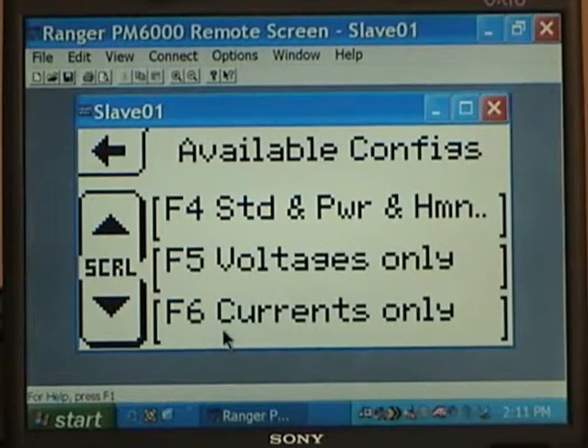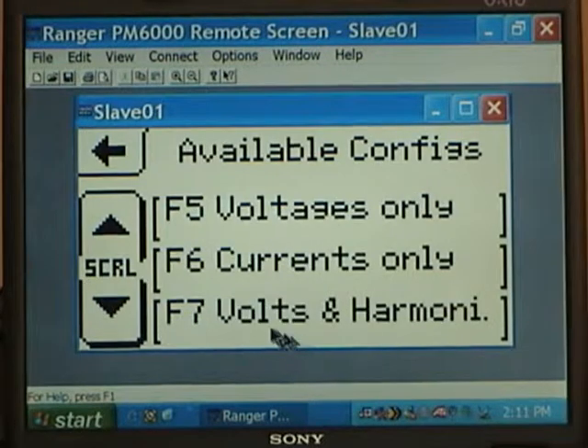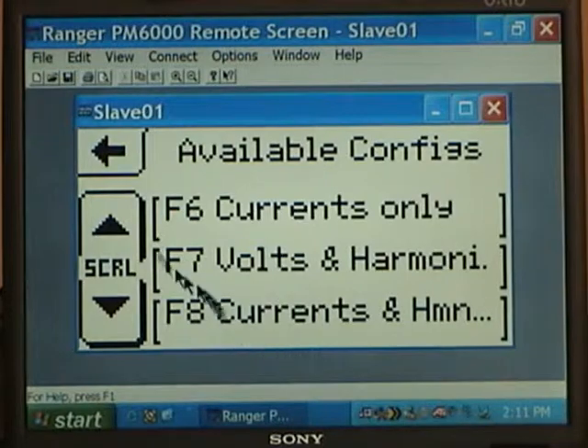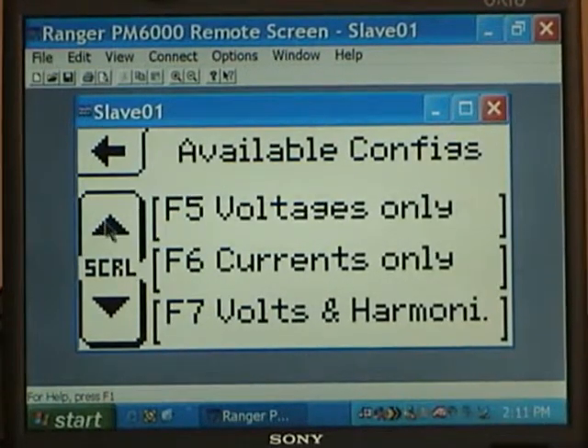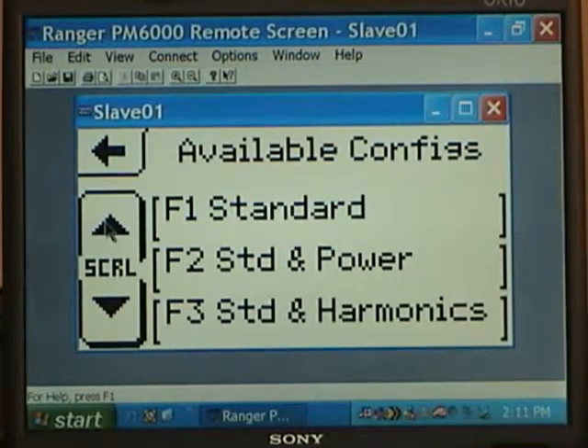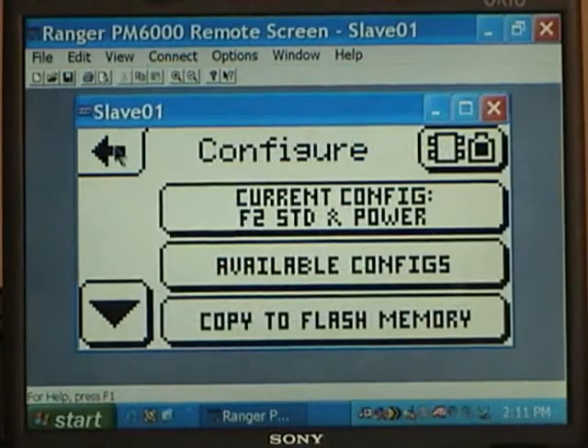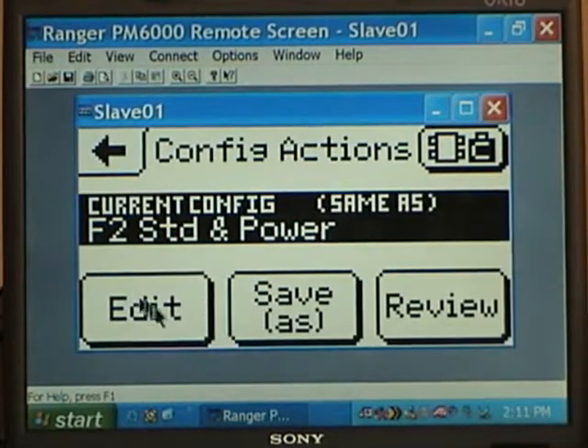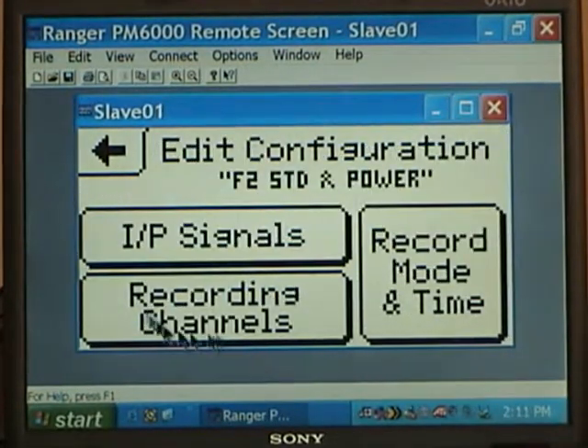Configuration number 6 is currents only. Configuration number 7 is voltage and harmonics. And configuration number 8 is current and harmonics. Most of the time, we think that most people would be using the standard, or standard with power, or standard with harmonics. Configuration number 1 is standard 3 voltages and 2 currents. I misspoke.